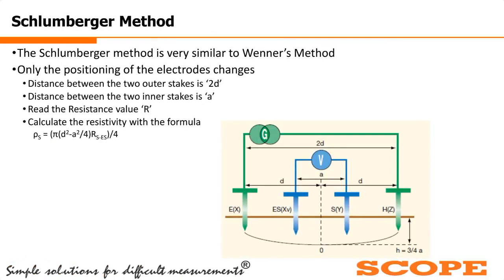Then the next one is the Schlumberger method. This method is similar to Wenner's method, but only the distance between electrodes is changed. How do we place these electrodes? Let us consider the center point O as the zero point. From that we place the E and H electrodes at a distance d from the zero reference point, and then we place the ES and S voltage electrodes at a distance a by 2 from the zero reference point.